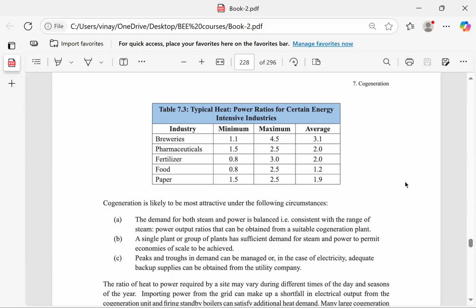Cogeneration is likely to be most attractive when the demand for both steam and power is balanced, consistent with the range of steam to power output ratios obtainable from a suitable cogeneration plant. If you can match the industry's requirement for electricity as well as process heat, the best approach is to design a cogeneration plant completely matching the load requirements of that industry.